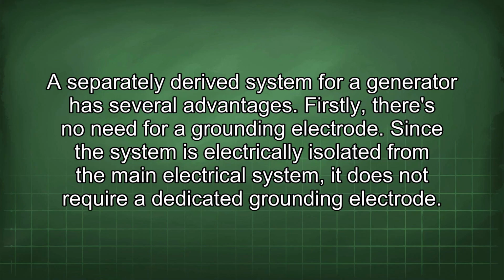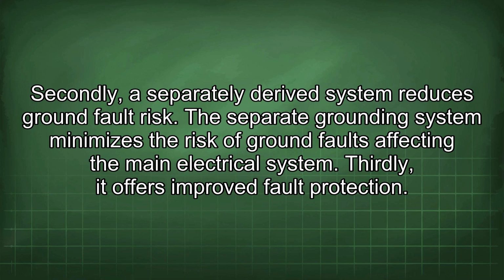A separately derived system for a generator has several advantages. Firstly, there's no need for a grounding electrode. Since the system is electrically isolated from the main electrical system, it does not require a dedicated grounding electrode. Secondly, a separately derived system reduces ground fault risk. The separate grounding system minimizes the risk of ground faults affecting the main electrical system.